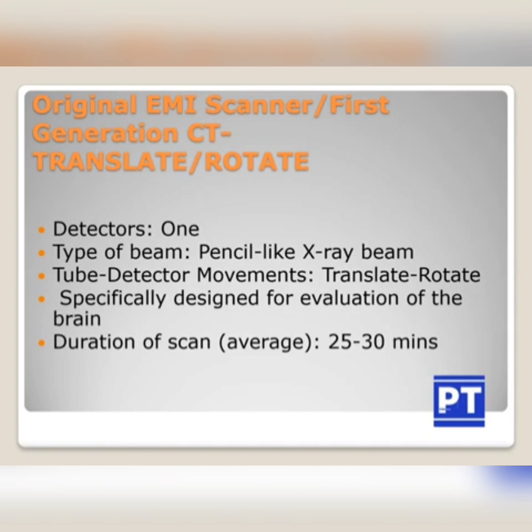In the case of first generation CT, there was only one detector. The type of beam was a pencil-like X-ray beam. The tube-detector movement was translate-rotate, and it was specially designed only for the evaluation of the brain. The duration of the scan was about 25 to 30 minutes.